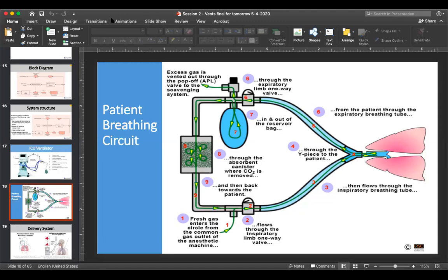Good. So the next question from the chat is from Dr. Innocent Kizima. Since the anesthesia machine is not designed for use for long hours, how will this change its preventive maintenance pattern? Really good question. Yeah, Innocent, this is a great question. And so for the anesthesia machines themselves, every 24 hours, we have to do a reset. You have to recalibrate the machine itself.